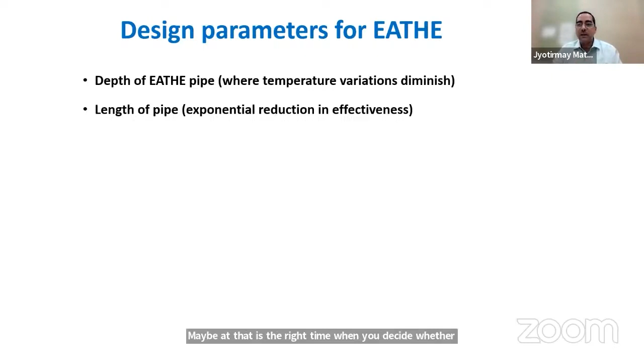The tendency of temperature heat exchange basically follows an inverse exponential curve. So after a certain time, where the exponent curve touches its knee point, the cost economics of every incremental length of pipe deteriorates. You have to cut down where the economics works out, and that is when you decide whether to go for one pipe or parallel two pipes. That's where optimization and calculations play a very important role.